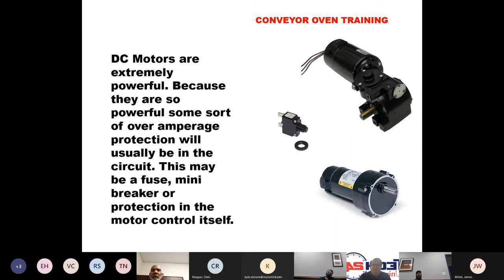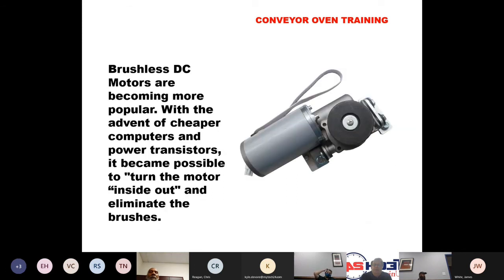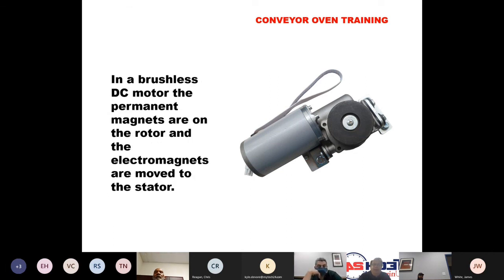DC motors are extremely powerful. And because they're so powerful, there's going to be some sort of over amperage protection to take it out of the circuit. This is usually going to be a fuse or a mini breaker, or there may be some kind of protection in the motor itself. Newer motors that we're seeing are brushless DC motors. They're becoming more and more popular. With the advent of cheaper computers and power transistors, it became possible to basically turn the motor inside out, eliminate the brushes. In a brushless DC motor, the permanent magnets are on the rotor and the electromagnets are moved to the stator.